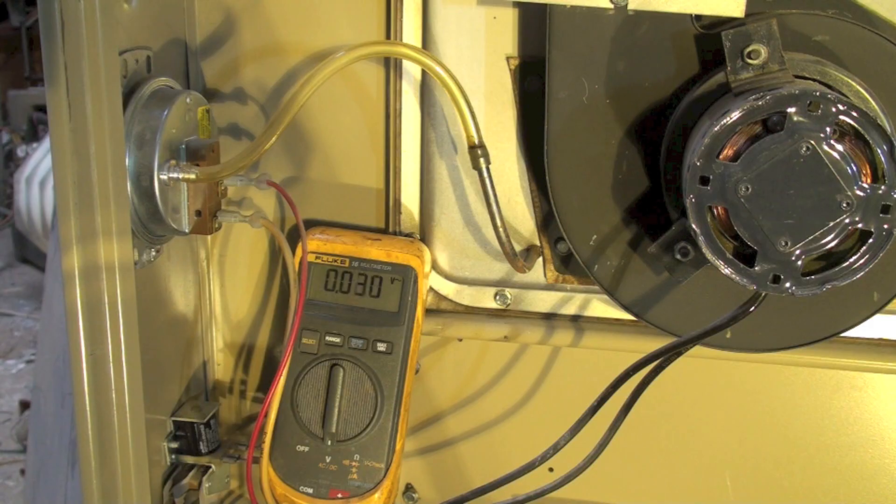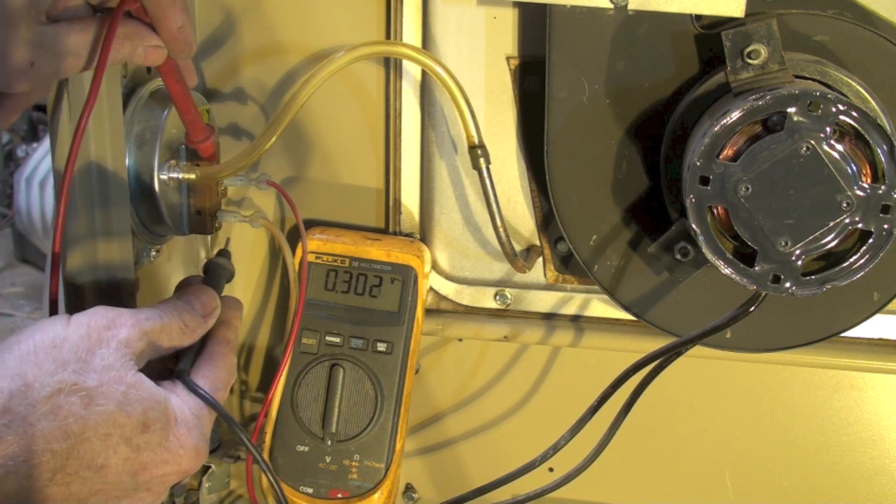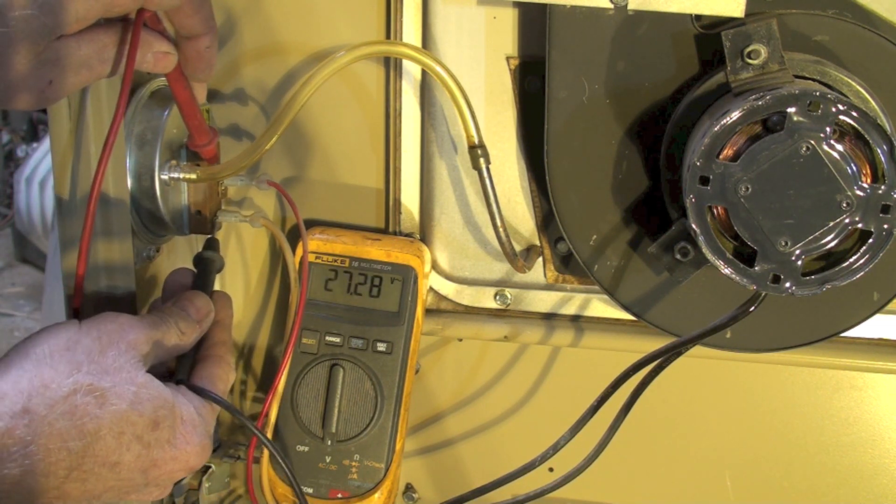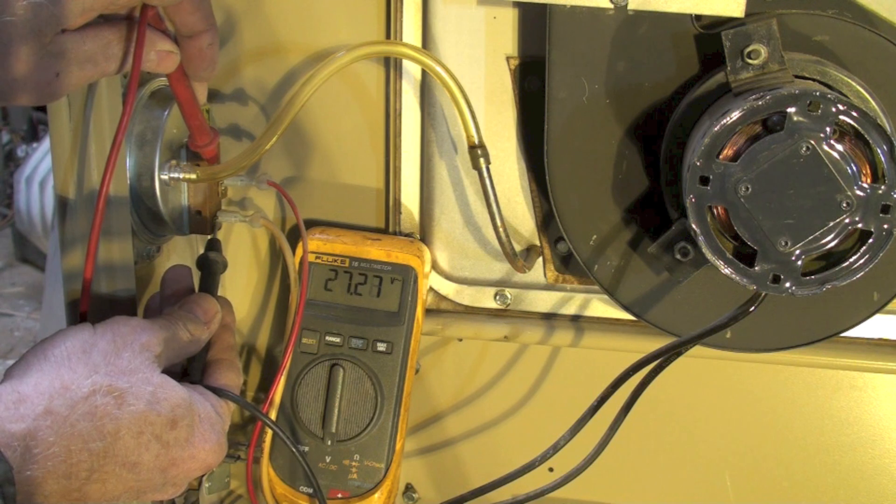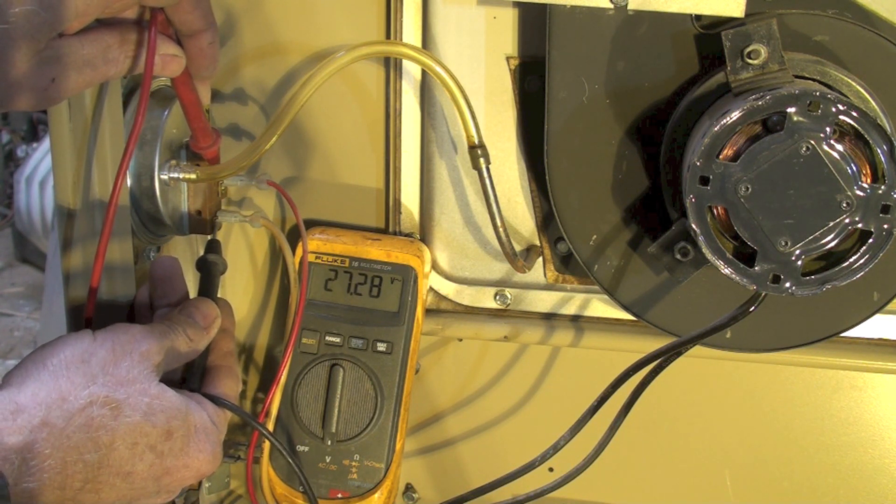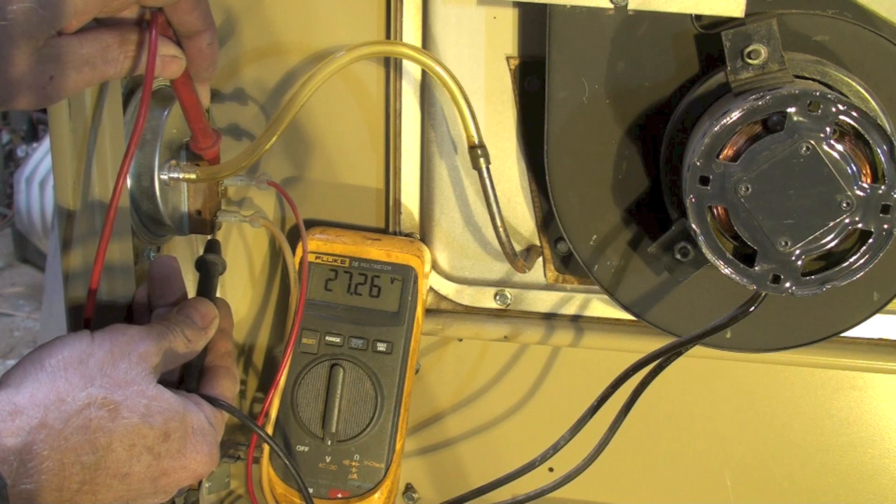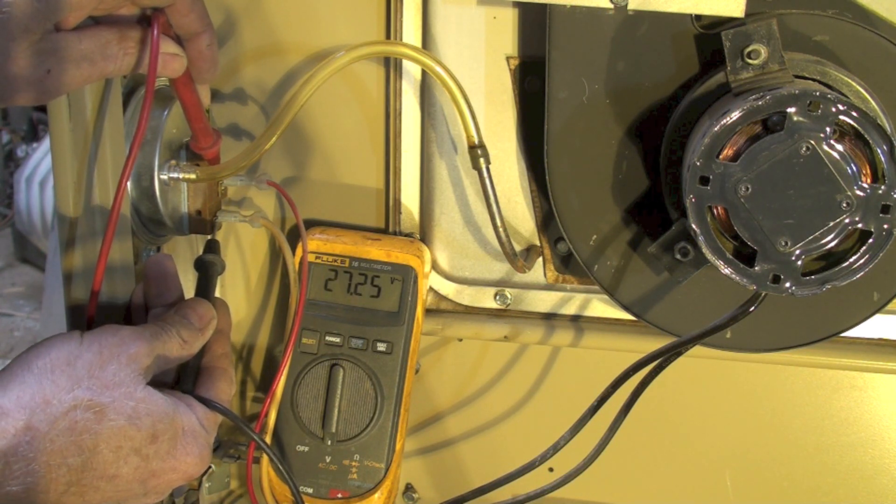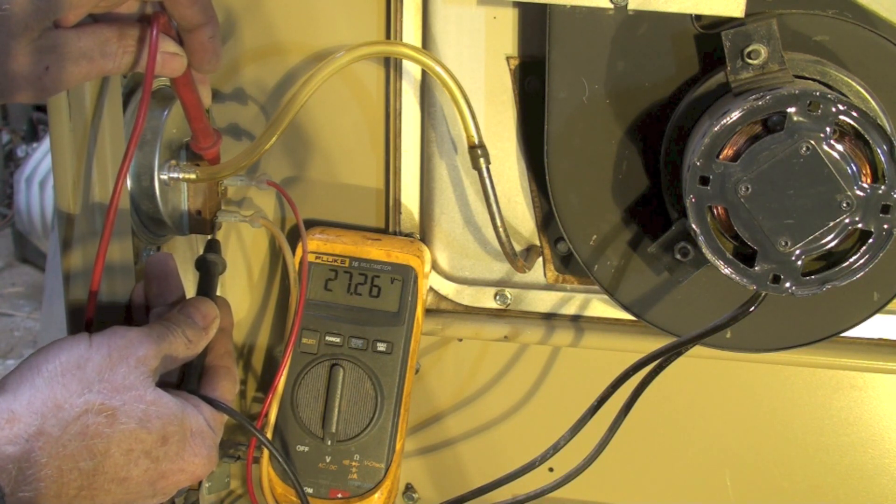Let's find out. Okay, I'm gonna go across here. Now you can see I'm showing a voltage. That means the pressure switch hasn't closed, because if it had closed I would read zero across the pressure switch. So what's wrong?